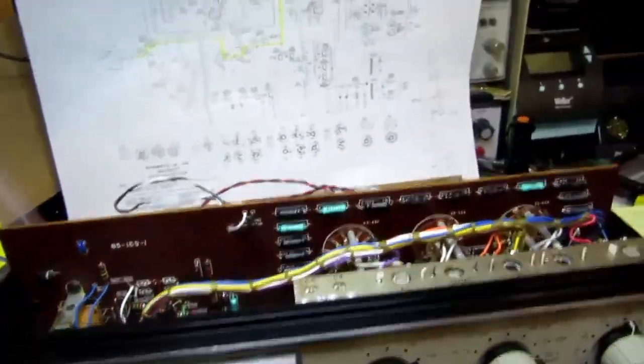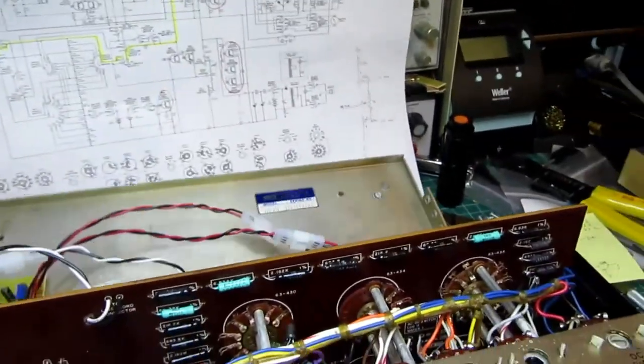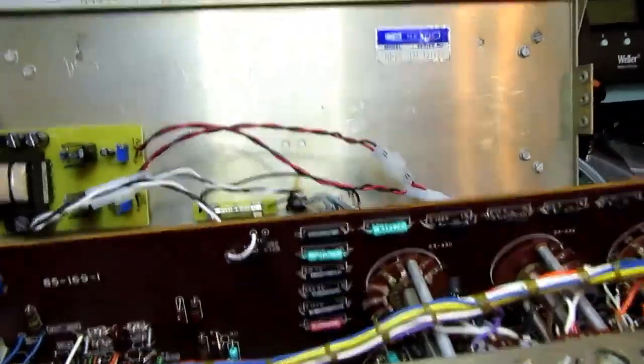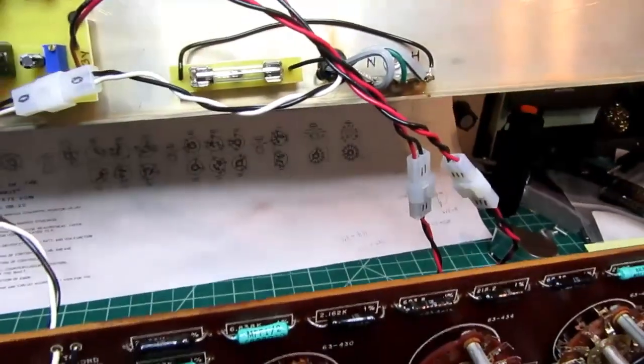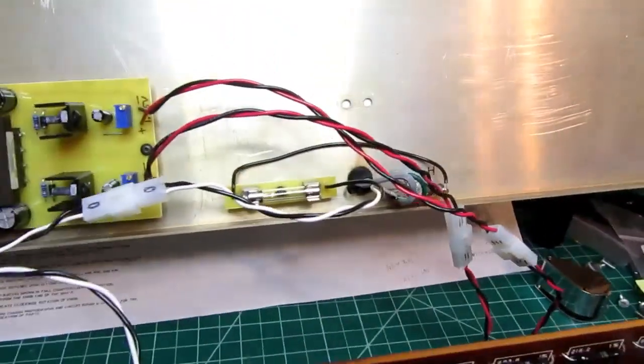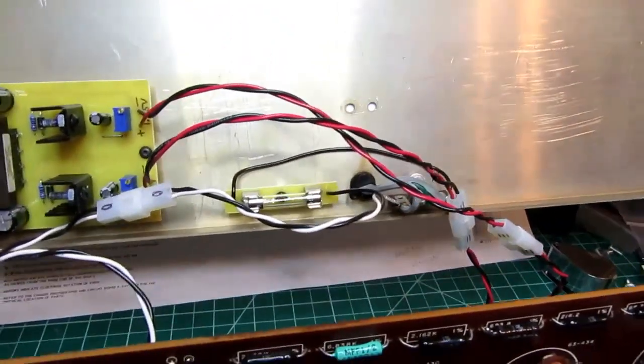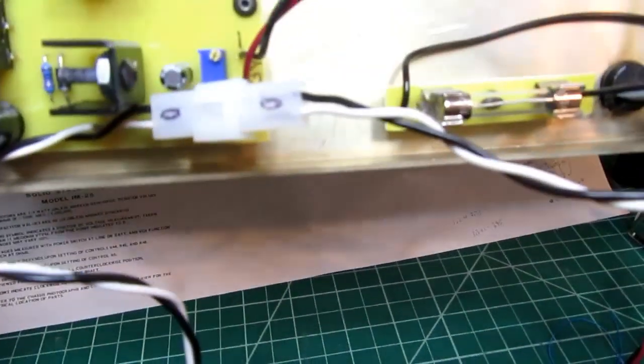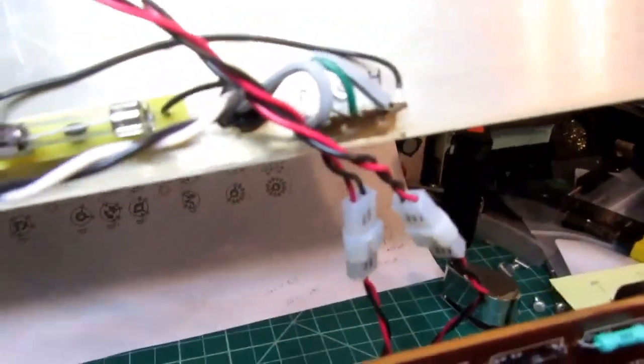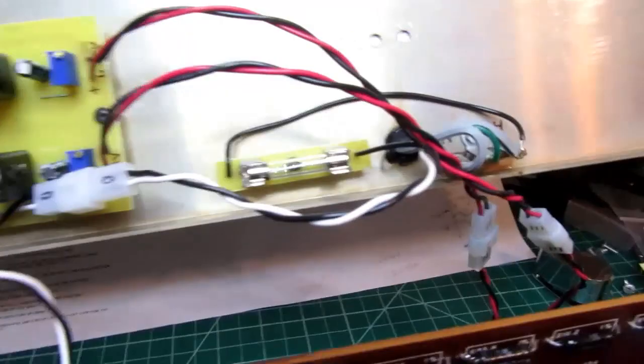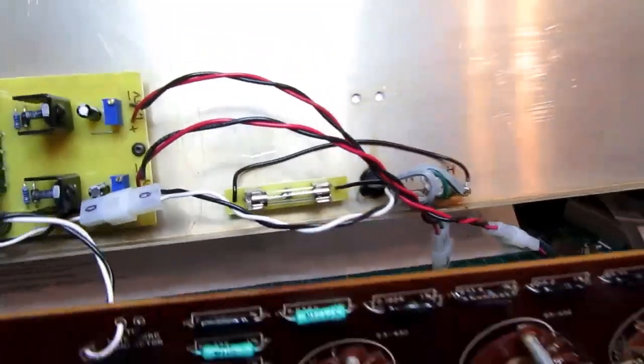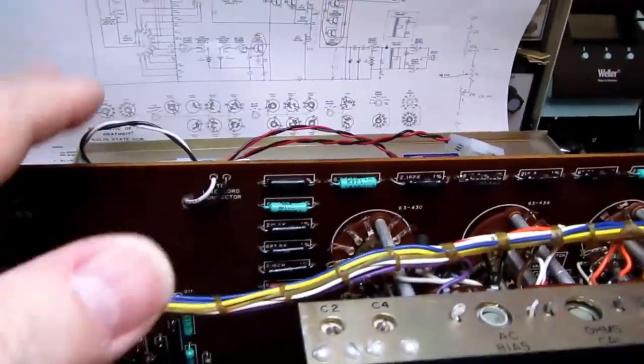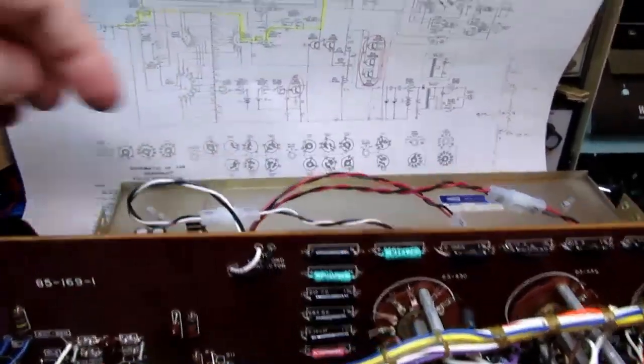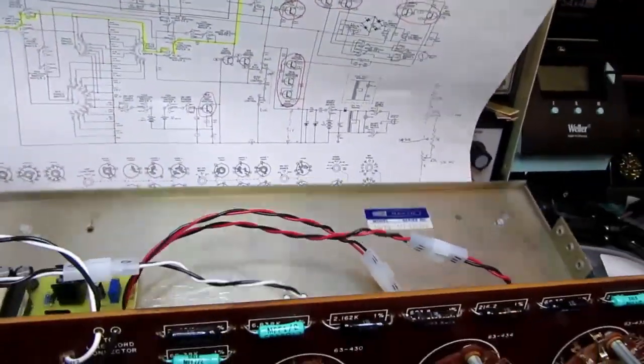As for the back panel, now this one's been modified by me to have extra wires going between the back panel, so it's easier to pull it further away from the meter for servicing. Actually, I put Molex plugs on each of the 2-wire sets so they can be unplugged and taken far away when you're trying to troubleshoot this part or change components out. You don't need this big thing flapping in the breeze.